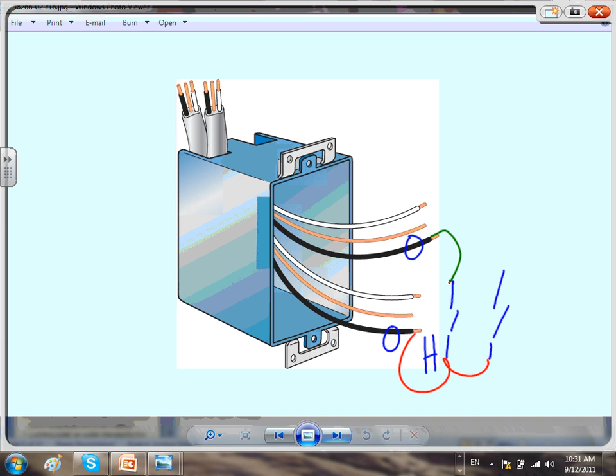I have one neutral - can I use the second conductor to identify it now, for the second switch? Based on this wiring, can I take this one as a switch leg to the fixture? No, you can't, based on this wiring method, because they can't share it. So you have to bring this one here and identify it as a hot. You re-identify the white as a black, bring the power to the switches, and from there take the power to the two lights - you have to have a neutral conductor.